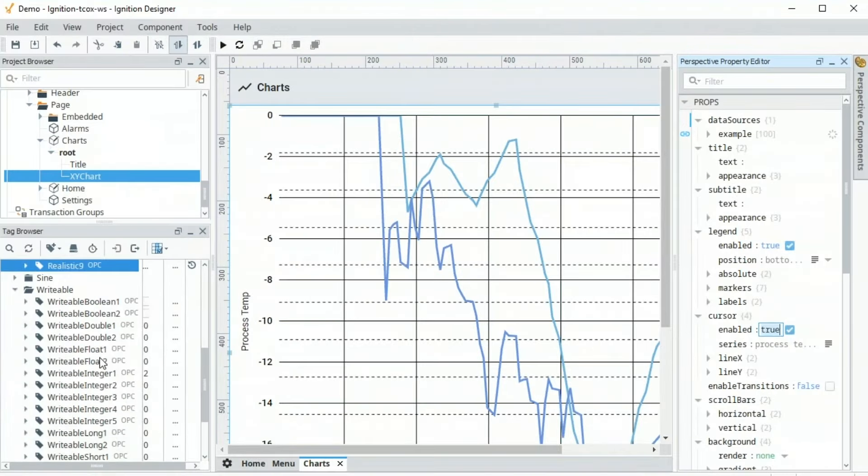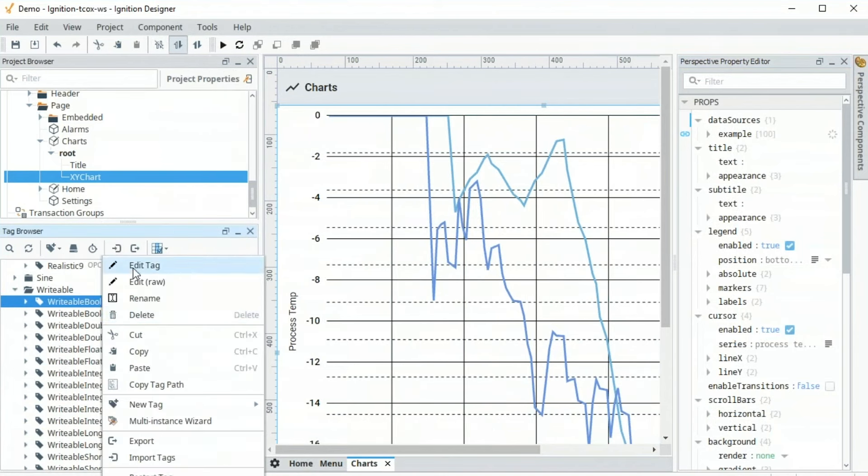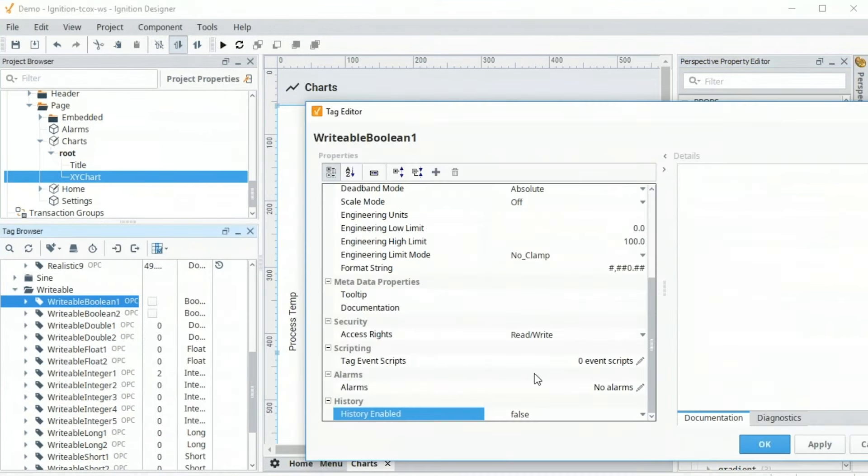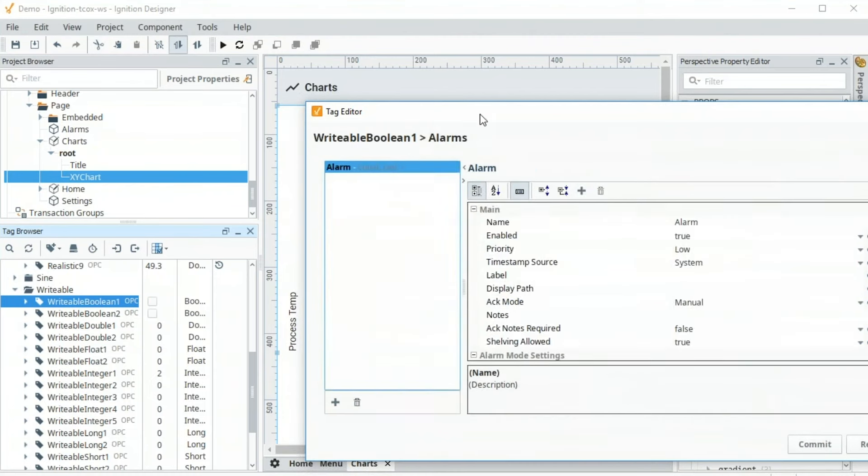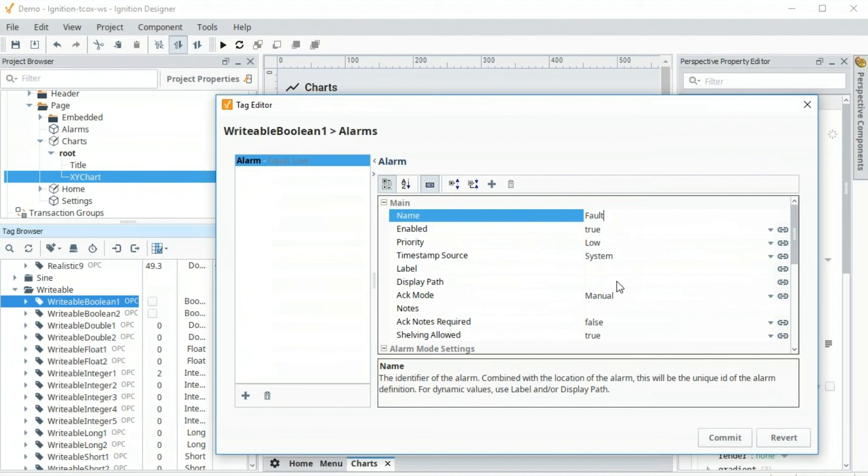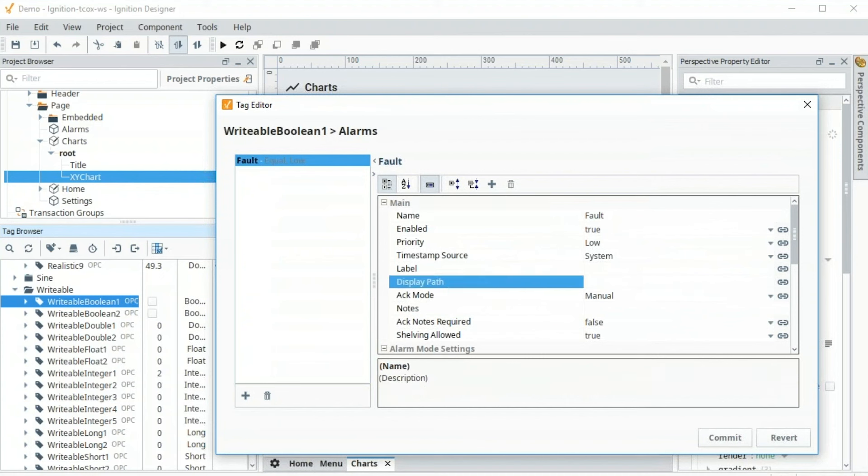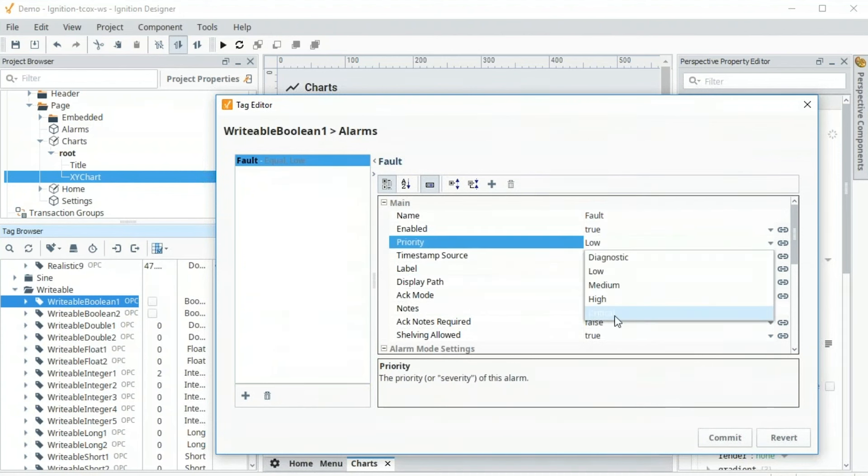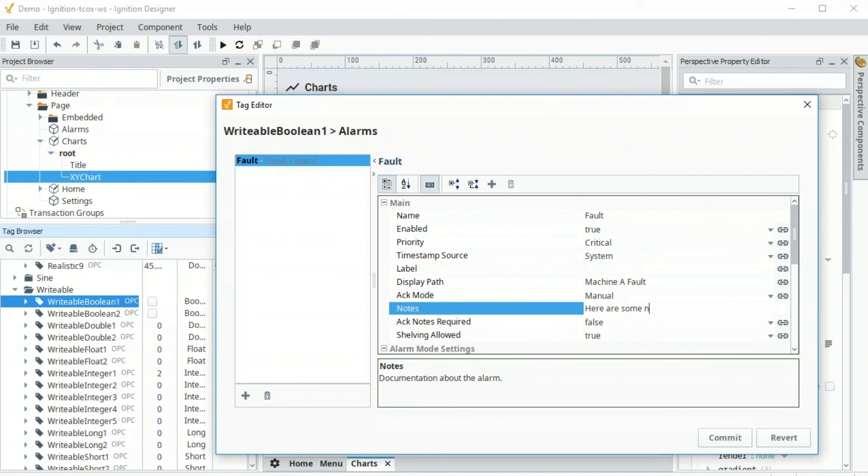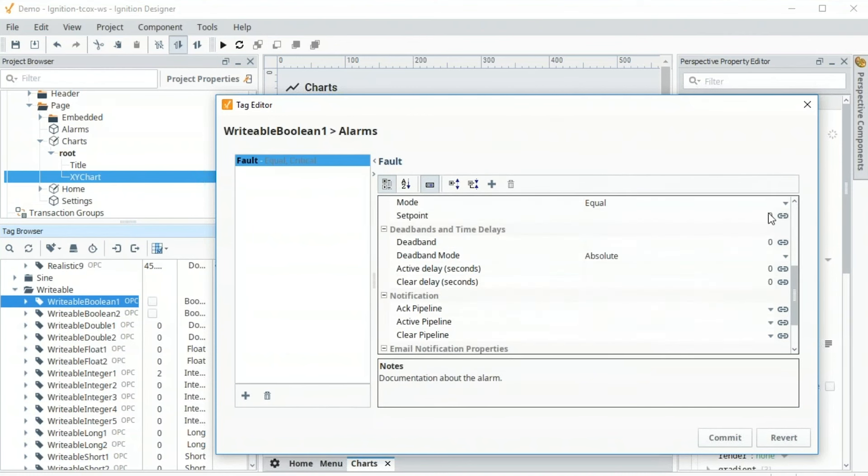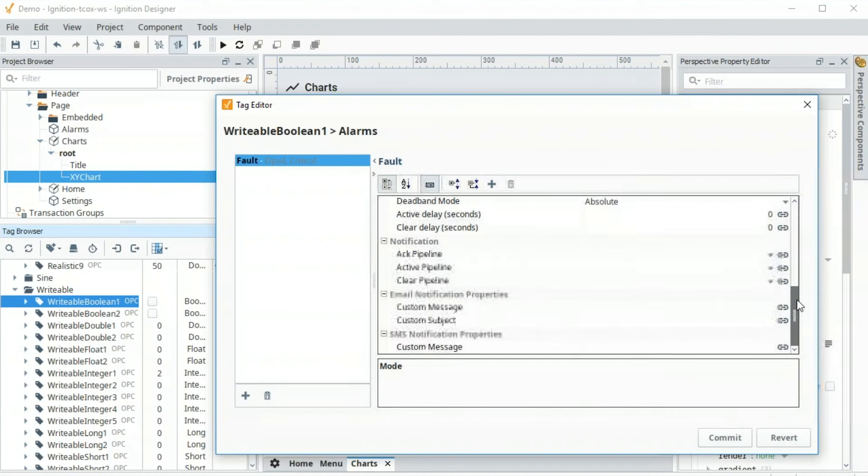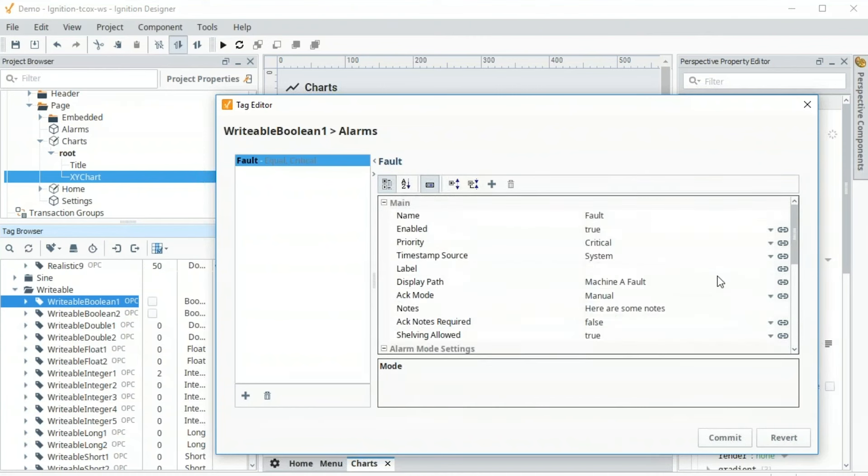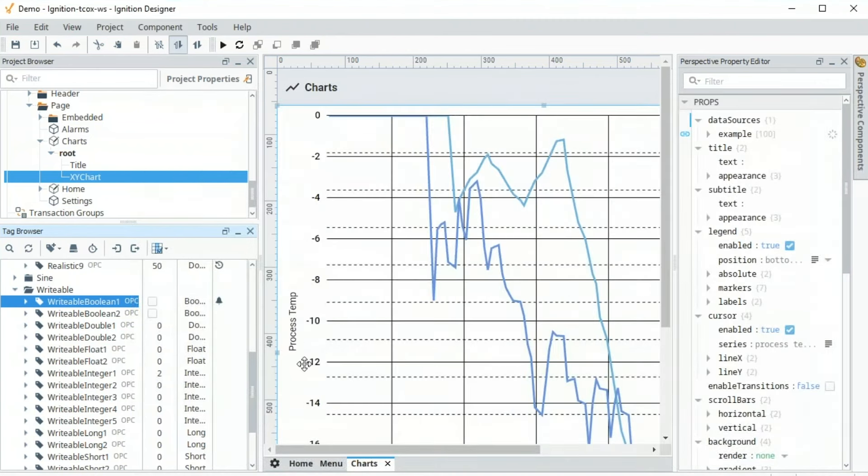The last thing we want to show is doing alarm. So I'm going to go to this writable Boolean 1, right-click, edit, and I'm going to turn on alarm, create an alarm. I'm going to have one or more alarms on there. I'll call this a fault, and I'll do the display as machine a fault. I'll make this maybe a critical alarm, and I can put some notes. Here are some notes, and we'll make it active when equals to 1. There's a lot of conditions you can put in here for when that alarm is going to be active, and there's dead bands and delays. Of course, we can also notify people through email, SMS, and voice when these alarms occur and have all these events being logged in the database, as we saw earlier. Let's just configure this. Press OK. Now I've got that alarm configured.